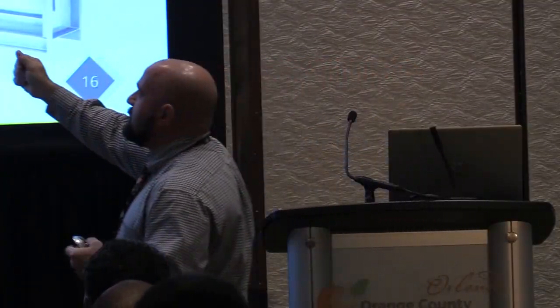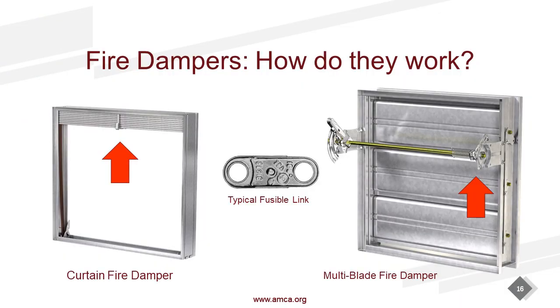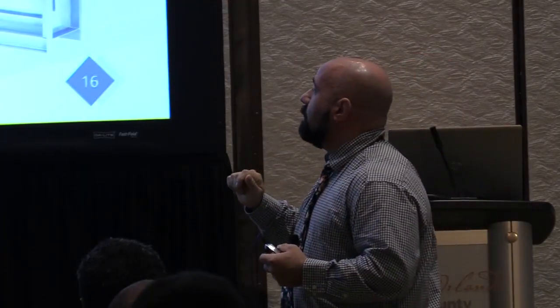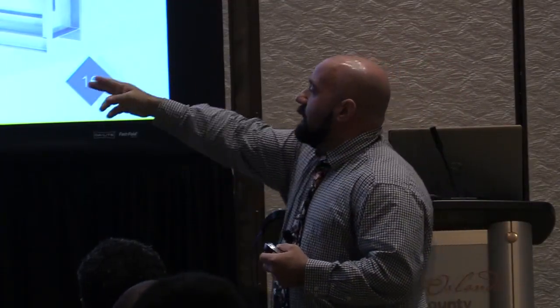It's a fusible link. It's a mechanical closure. There's no electric actuator. There's no pneumatic actuator. It is a bimetallic disc. It's got a solder that holds it together. That solder melts at the specified temperature. Building code says minimum 50 degrees above ambient, minimum, and I think it's 160 degrees minimum, right? So on a curtain fire damper, it's very simple. There's a fusible link. There's a blade pack. That's an accordion-style blade pack. When that fusible link melts, it just drops.